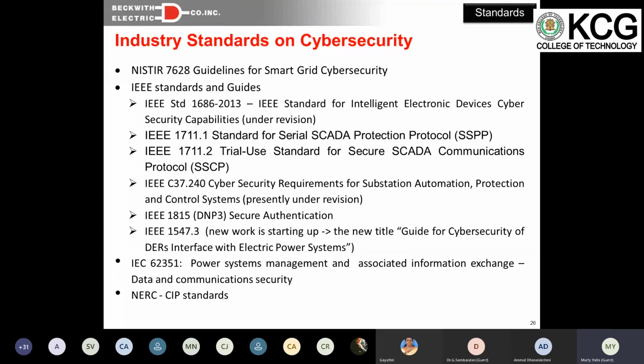If you have a serial link, like 232 or 485, there's IEEE standard 1711 for use with IEDs or SCADA communications; it's being revised right now. Then IEEE standard C37.240 covers cybersecurity requirements for substation automation, protection, and control devices inside the substation. That is also under revision, again within our group, PSCC and IEEE PSRC.